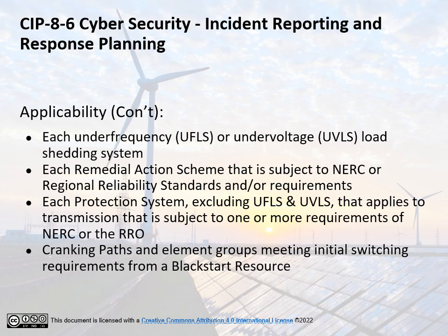Each protection system excluding UFLS and UVLS that applies to transmission that is subject to one or more requirements of NERC or the RRO. Cranking paths and element groups meeting initial switching requirements from a black start resource up to and including the first interconnection point of the starting station service of the next generation units to be started.